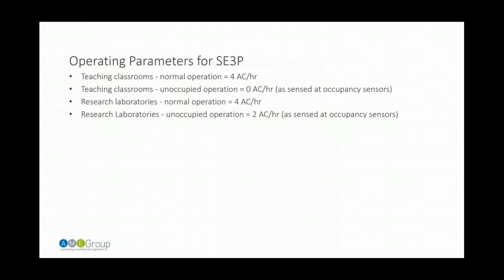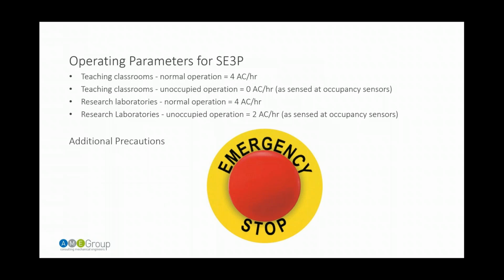And in the research labs, we're going to be ramping down to about 2 air changes to make sure that we keep getting airflow in those labs. And again, occupancy sensors are doubled up on the lighting sensors, just to kind of piggyback on systems that are already there. Additional precaution in each lab is the emergency stop. And so we've made sure that the emergency electrical cutoff that we've got in each lab is connected to our ventilation systems. And if somebody presses that button, it's just going to open up all of our exhaust and our supply air and just ventilate the room as much as it can.